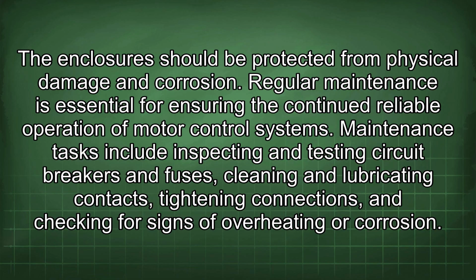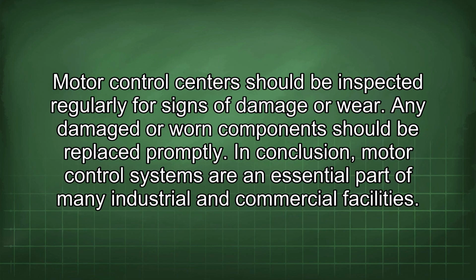Regular maintenance is essential for ensuring the continued reliable operation of motor control systems. Maintenance tasks include inspecting and testing circuit breakers and fuses, cleaning and lubricating contacts, tightening connections, and checking for signs of overheating or corrosion. Motor control centers should be inspected regularly for signs of damage or wear. Any damaged or worn components should be replaced promptly.